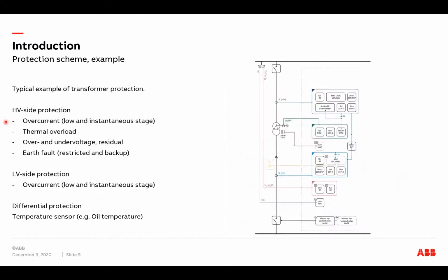But generally, when we look at it from the protection relay perspective, we can say, like we have here in a typical example, that since we are measuring the current from both the high voltage and low voltage side, we use different protections for these current measurements.